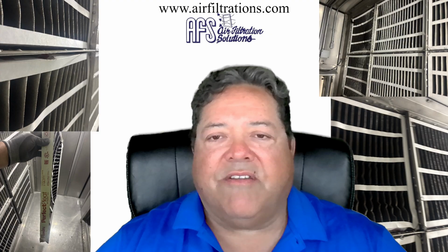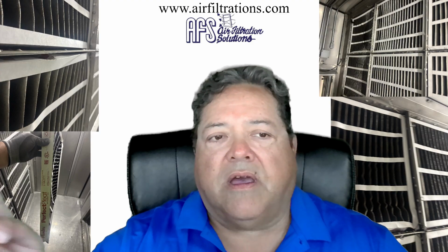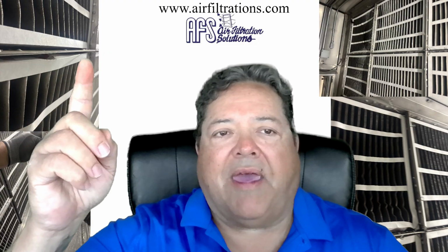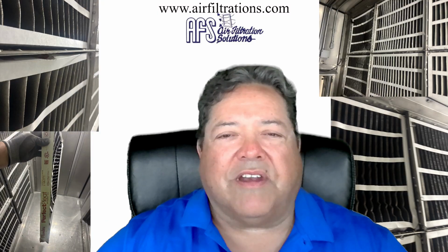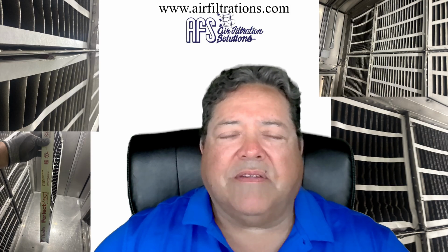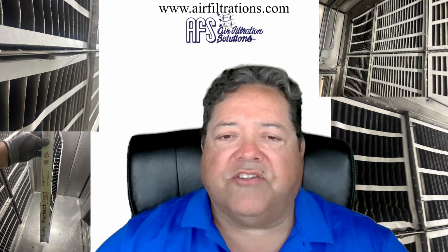And pleated filters, you could see here, I point out, not only do they collapse or show signs of buckling, you could see here the gaps, that's a lot of bypass there. You could see with this filter right here started to cave in a little. And once the contractors install these filters, they get it up and running, then they iron the bugs out a little bit, then they turn it over. When it's ready, they turn it over to engineering.